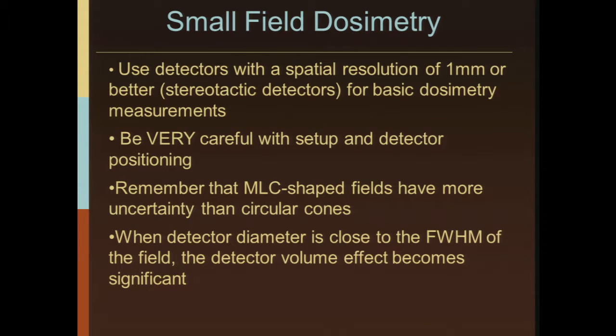Use detectors with a spatial resolution of 1 millimeter or better for basic dosimetry measurements - that was sort of a rule of thumb. Be very careful with setup and detector positioning. Remember that MLC shapes have more uncertainty than circular cones. Circular cones don't change, they're circular cones. They're not as popular anymore, but the physics was pretty easy to work out.